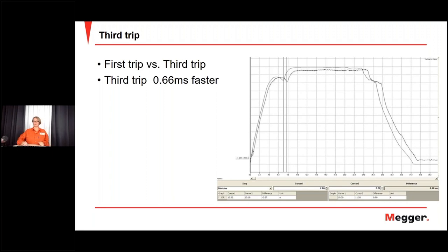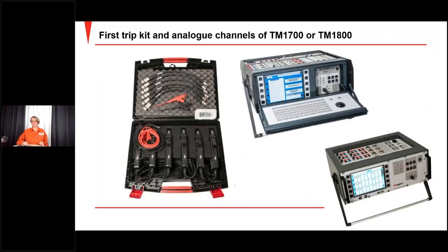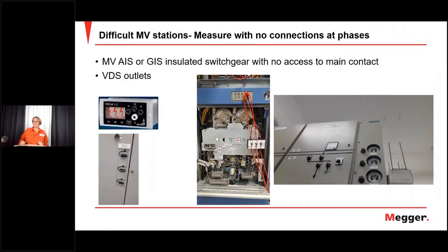So we detected that the circuit breaker was not in such a good shape. This is the equipment you use: an analyzer, either TM1800 or TM1700, and a first trip kit, which is current clamps. And I mentioned this on Tuesday, but I don't know if everybody was attending then, that you can also measure difficult circuits with medium voltage by measuring the online measurement without connecting at the phases. And that's possible when we have this type of outlets, VDS outlets. We have another type here and a third type here.